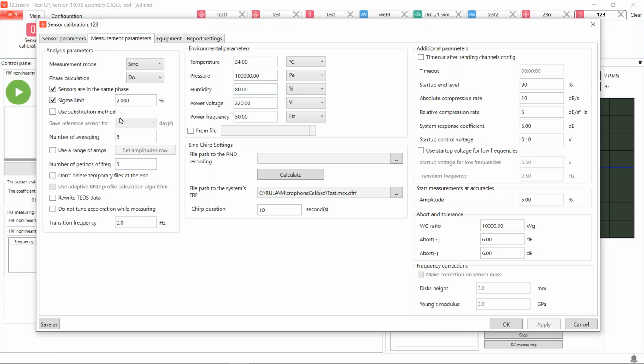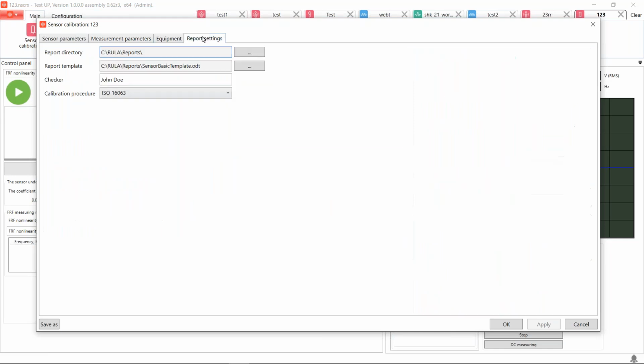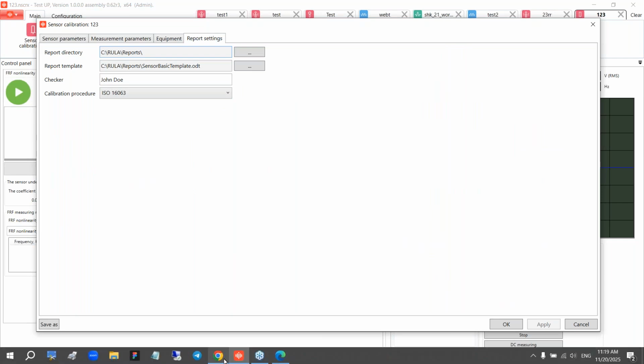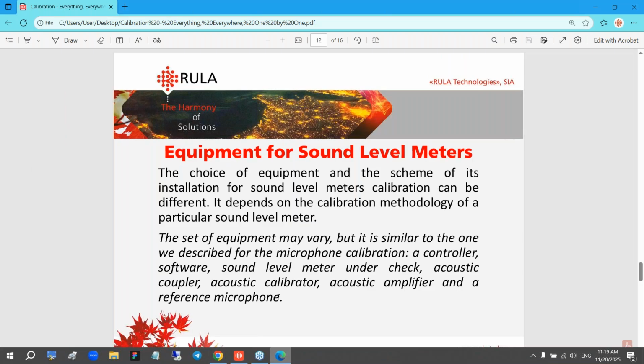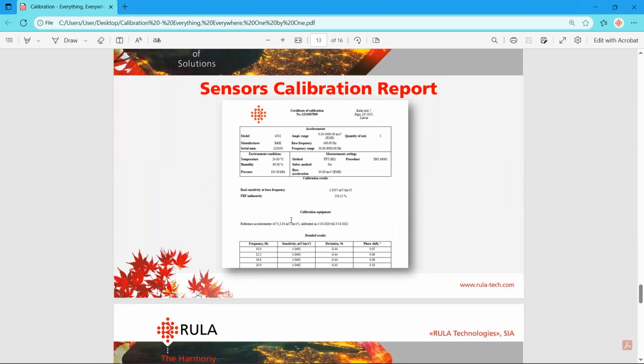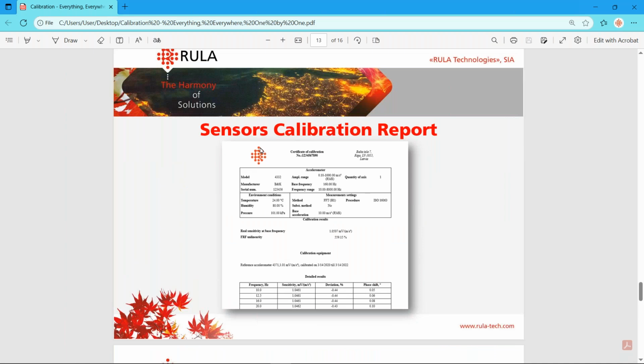After any calibration, TestUp automatically creates a report, which includes measurement results in the form of tables and graphs, detailed information about the reference sensor, calibration date and place. And I would like to open the presentation to show you the way it looks. So as I said, you can find in the report the model of the sensor, the manufacturer, all the parameters you need, you got after the calibration procedure. Now let's move on.